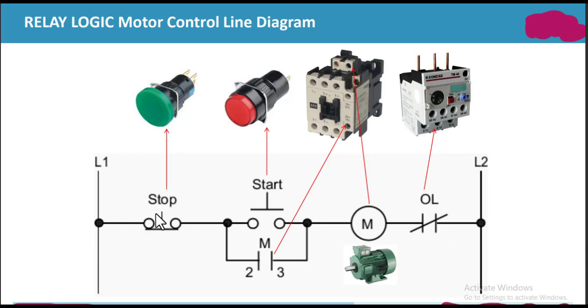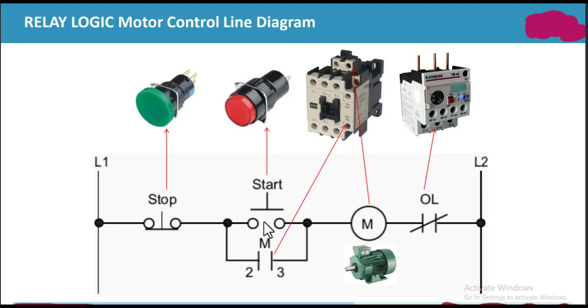This is the stop switch, which is a normally closed switch, so current can flow through it. This is the start switch, which is normally open — it is a push button, so normally current cannot flow through it. When we press this switch it will be turned on and then current can flow through it.